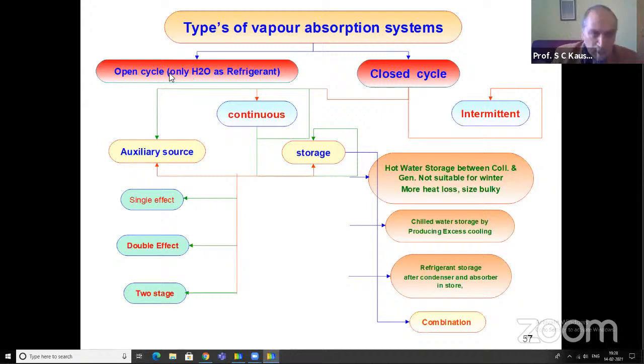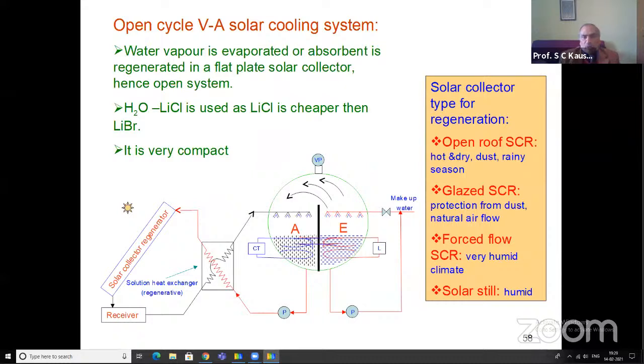So these open cycle vapor absorption systems are suitable to provide air conditioning and most suitable for providing solar air conditioning. Now, this is the basic principle of the open cycle vapor absorption solar cooling system, where the number of components is reduced. We may eliminate the condenser. So we may need only a solar collector regenerator to provide input heat for regeneration. But we actually have an absorber evaporator vessel, a combined vessel for the absorption process and the evaporation process, having a partition between them.